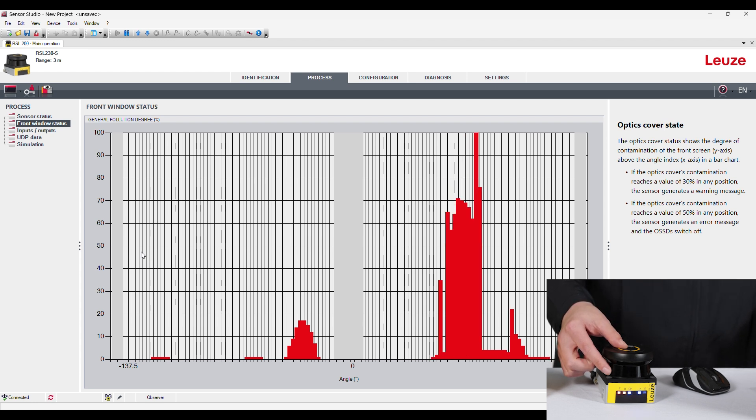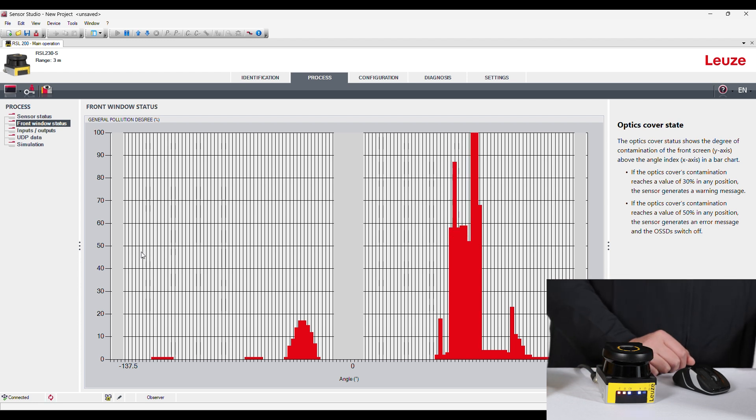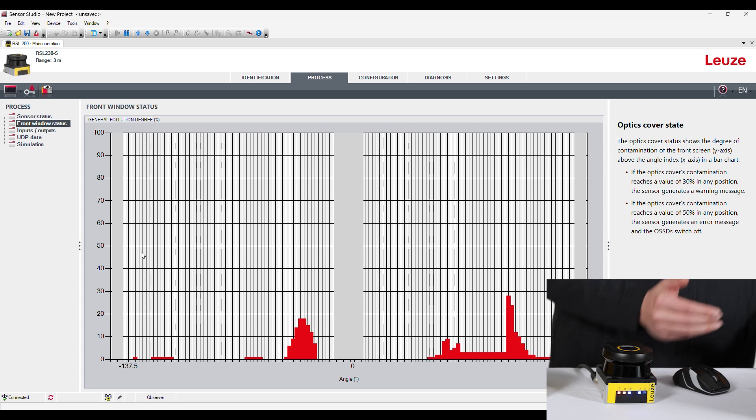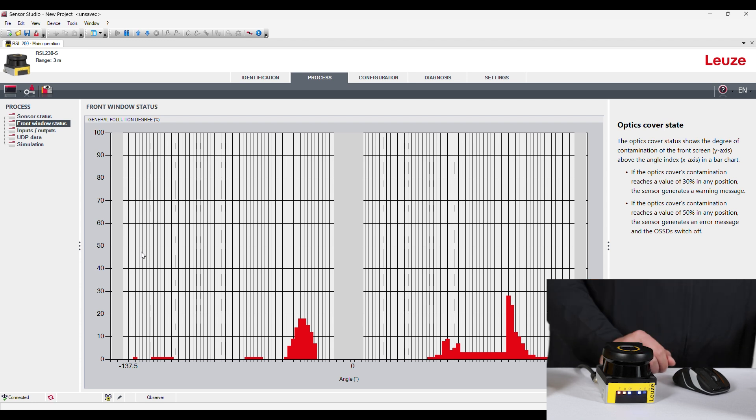So if we get above that 50% level there, it's actually going to turn off our OSSDS. So that's going to fault out the sensor and you're going to have to actually go out there and clean it. But you can obviously hop on here and see where it is and where the issue is on the lens.